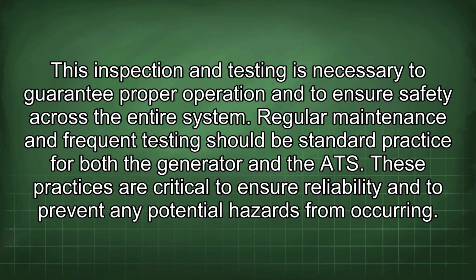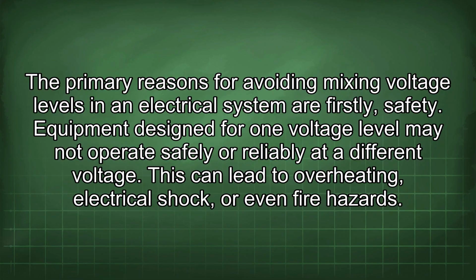Regular maintenance and frequent testing should be standard practice for both the generator and the ATS. These practices are critical to ensure reliability and to prevent any potential hazards from occurring. The primary reasons for avoiding mixing voltage levels in an electrical system are, firstly, safety. Equipment designed for one voltage level may not operate safely or reliably at a different voltage. This can lead to overheating, electrical shock, or even fire hazards.